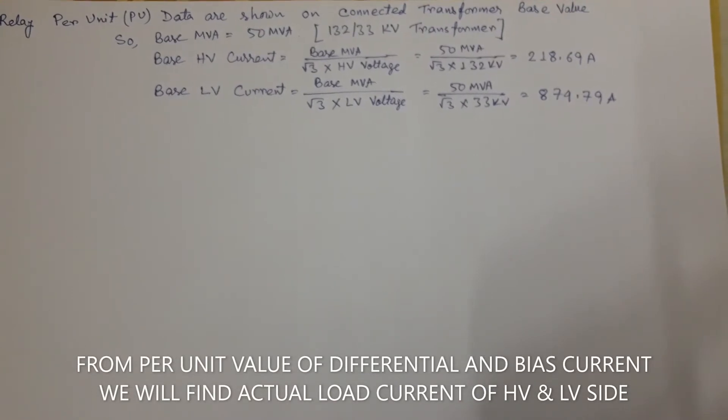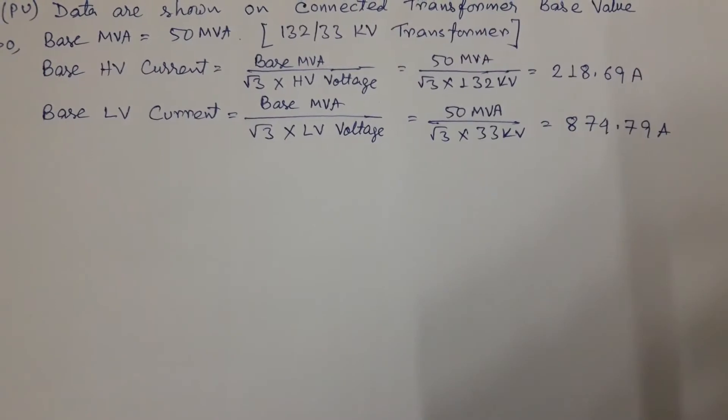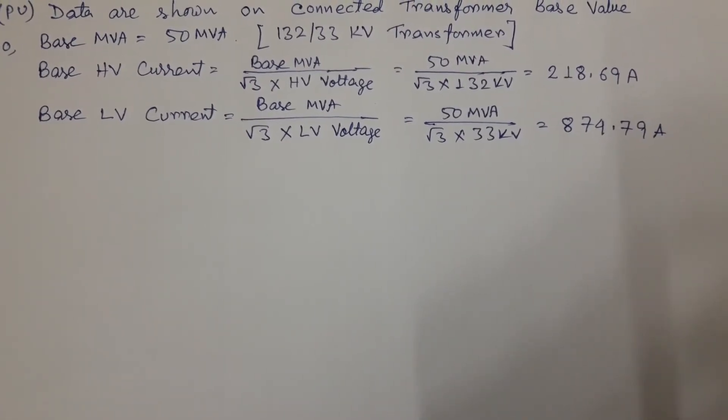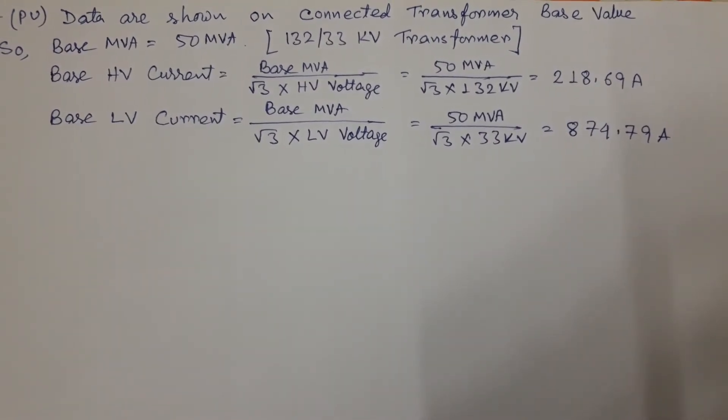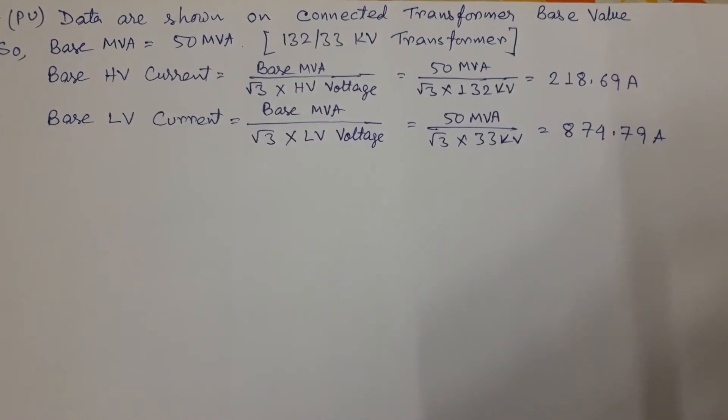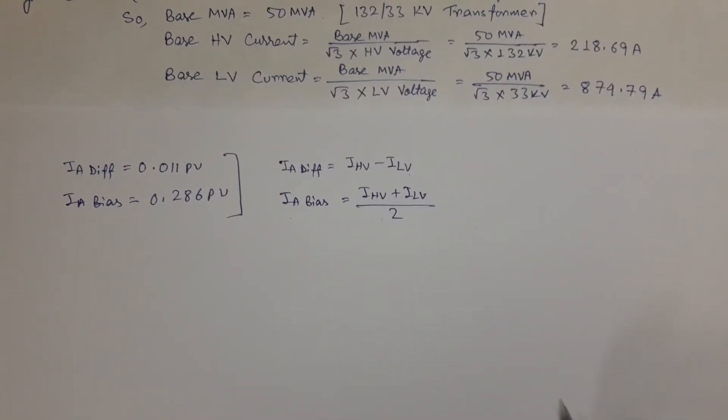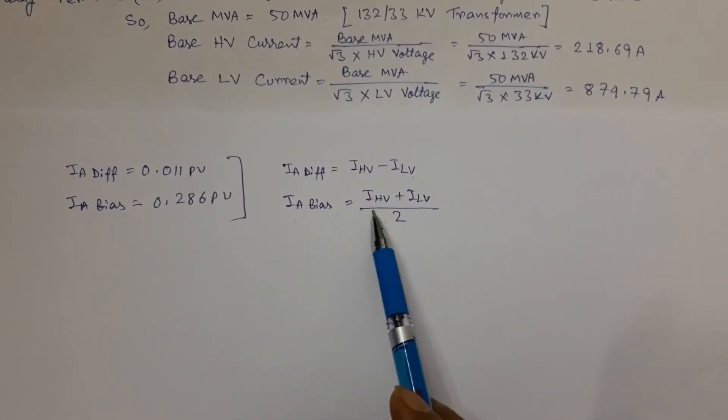Relay per unit data are shown on connected transformer base value. So HV side base current is 218 amperes, and LV side base current is 874.79 amperes. Now in relay, differential and bias currents are calculated separately for each phase by using these two formulas.